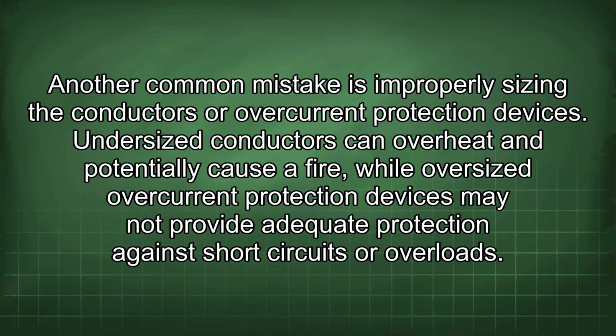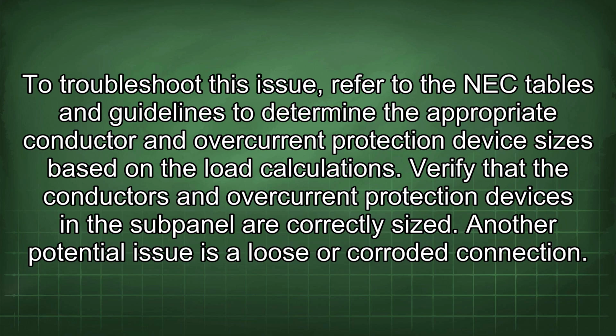Another common mistake is improperly sizing the conductors or overcurrent protection devices. Undersized conductors can overheat and potentially cause a fire, while oversized overcurrent protection devices may not provide adequate protection against short circuits or overloads. To troubleshoot this issue, refer to the NEC tables and guidelines to determine the appropriate conductor and overcurrent protection device sizes based on the load calculations. Verify that the conductors and overcurrent protection devices in the subpanel are correctly sized.